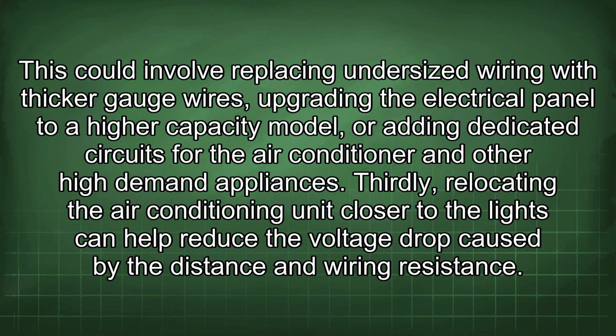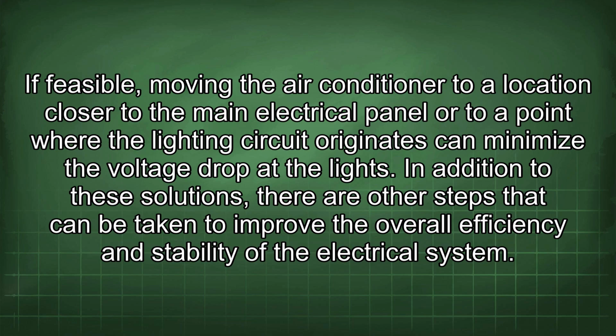Thirdly, relocating the air conditioning unit closer to the lights can help reduce the voltage drop caused by the distance and wiring resistance. If feasible, moving the air conditioner to a location closer to the main electrical panel or to a point where the lighting circuit originates can minimize the voltage drop at the lights.